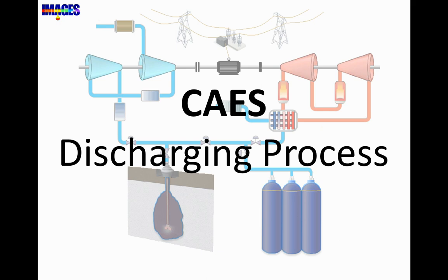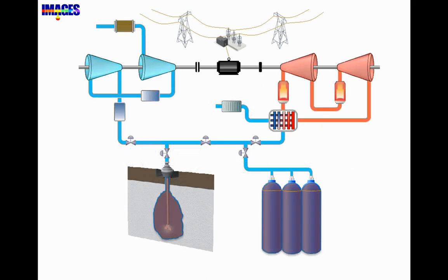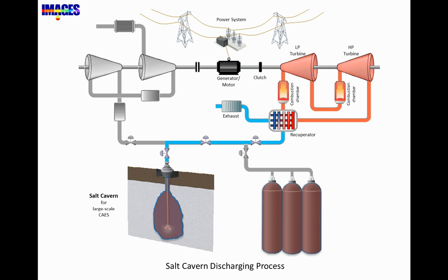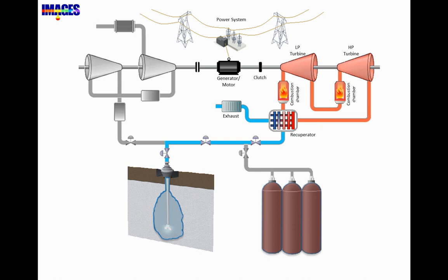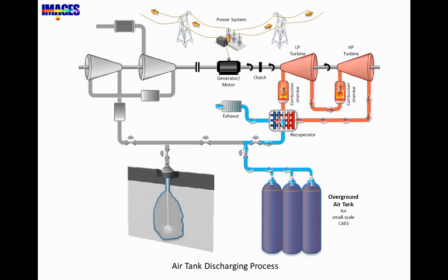Now let's take a look at the discharging process. When the power generation cannot meet the load demand, the stored compressed air is released and heated by a heat source, which can be the heat generated from the combustion of fossil fuel, or the heat recovered from the compression process. The compressed air energy is finally captured by the turbines. The waste heat from the system exhaust can be recycled by a recuperator unit. The same process takes place in the case of overground air tank discharge.